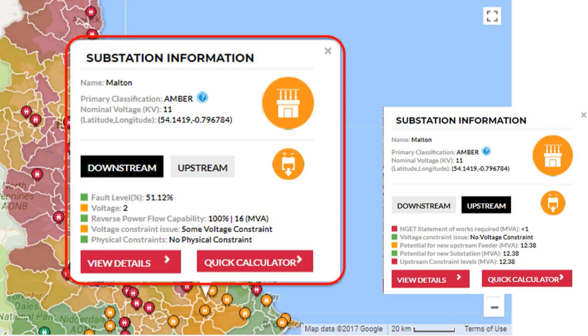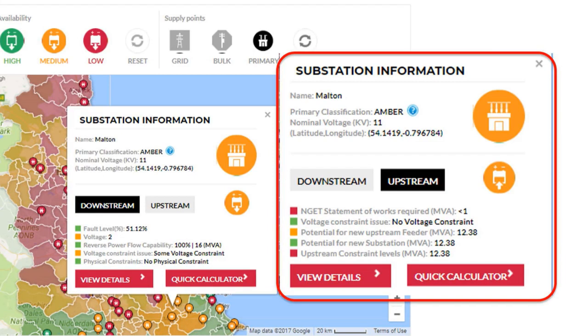If we click onto the upstream button, it gives us a bit more information about things upstream of the substation that could affect what we can do. The first one to note here is what we've called NGET statement of works. When we connect to the network, we're changing the national power flows right across the UK, even for small generation. A small generator may have no particular impact on that national picture, but as you get bigger, you have a greater impact.